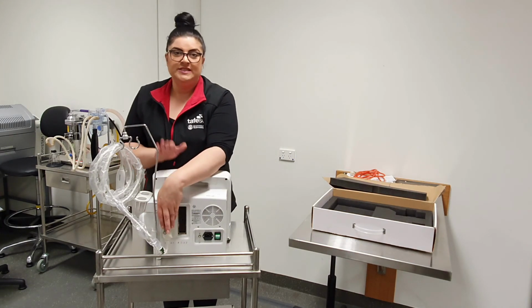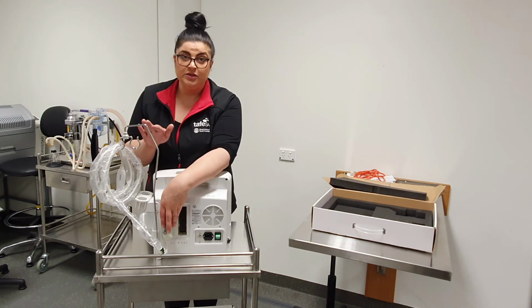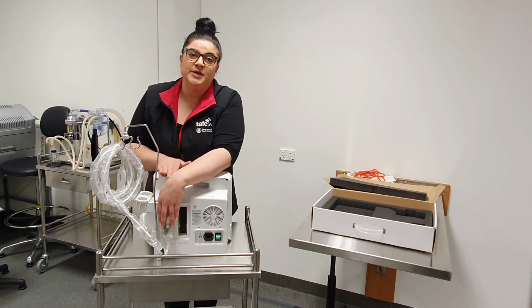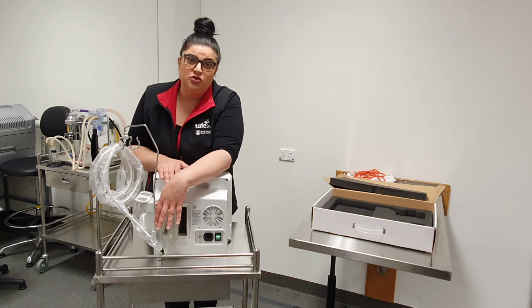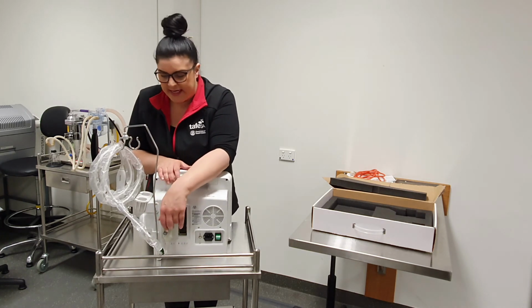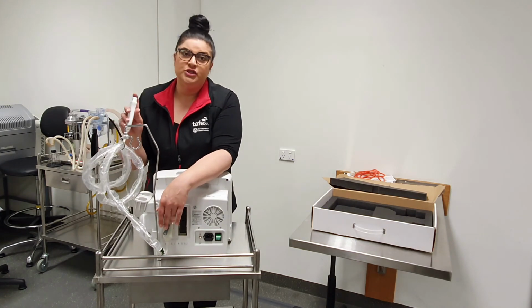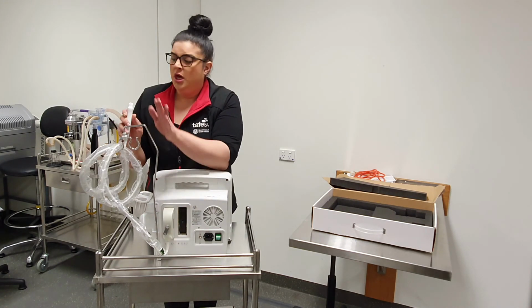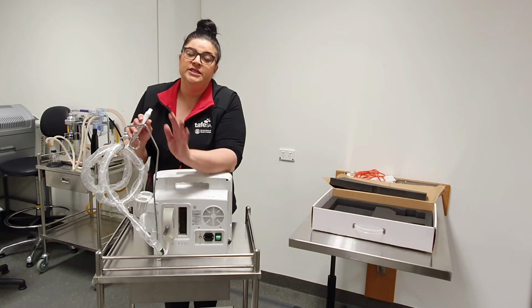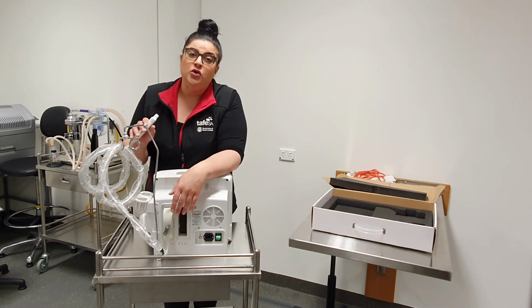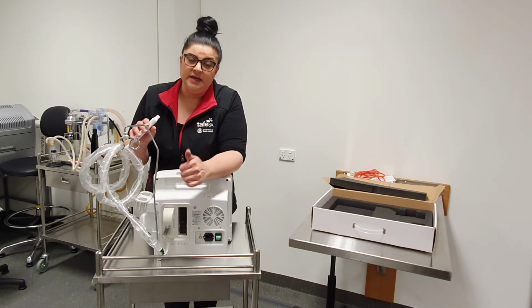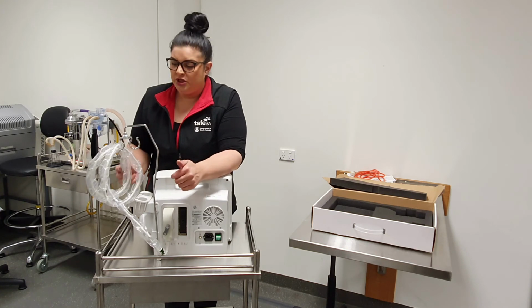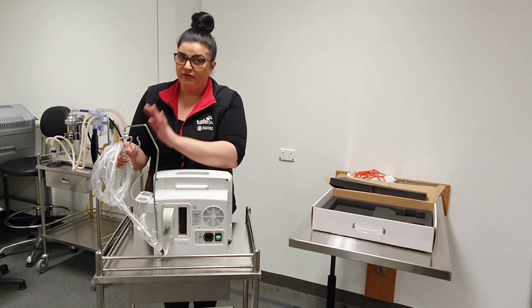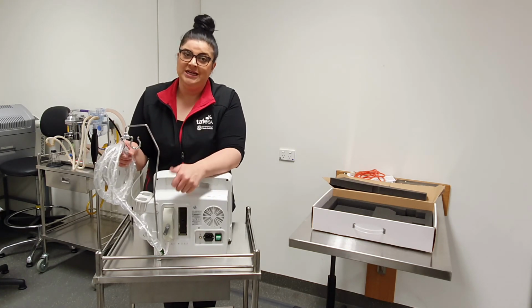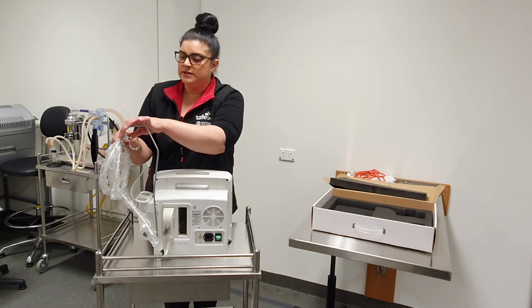Under normal circumstances, the transducer plus the cord and the socket all needs to be cleaned according to manufacturer's instructions before you put that away. If you leave your transducer probe covered in gel, I can almost guarantee at some point the machine will fail and you won't get contact with the skin and you won't get a nice ultrasound image. So please make sure before you put the probe away, you clean it as per manufacturer's instructions.